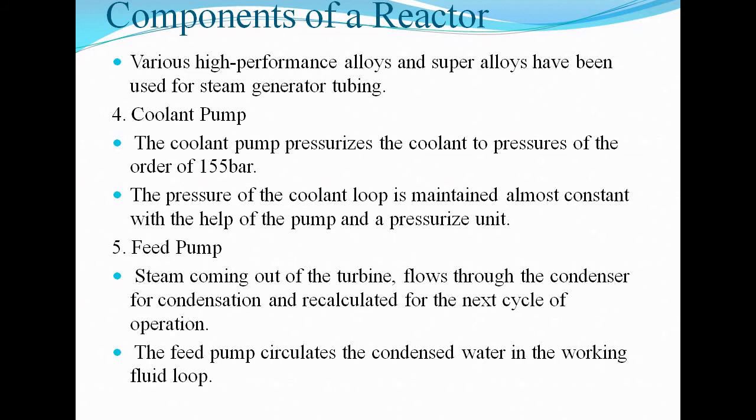The next one is coolant pump. The coolant pump pressurizes the coolant to pressures of around 155 bar. The pressure of the coolant is maintained almost constant with the help of the pump and a pressurizer unit. So a pressure of around 155 bar is maintained.